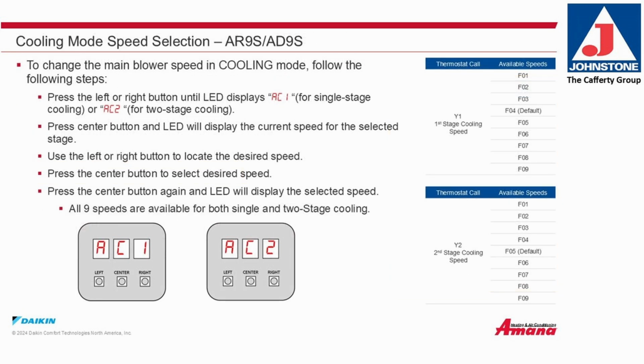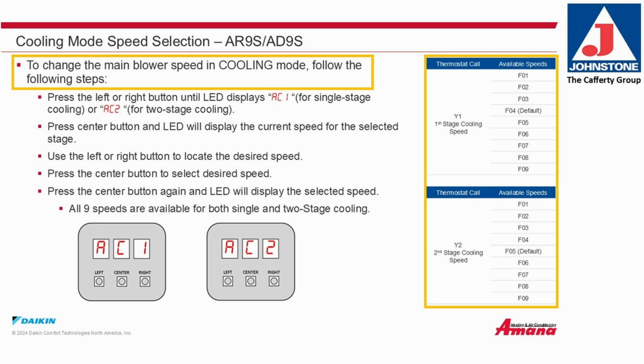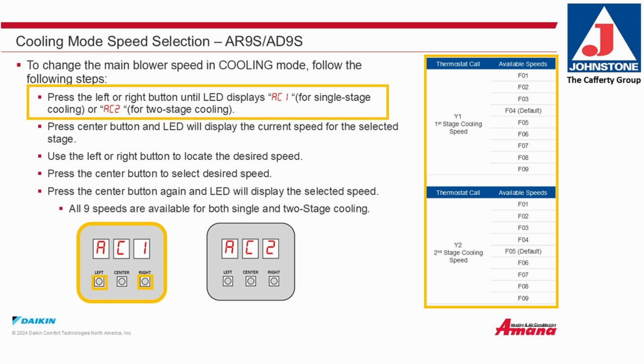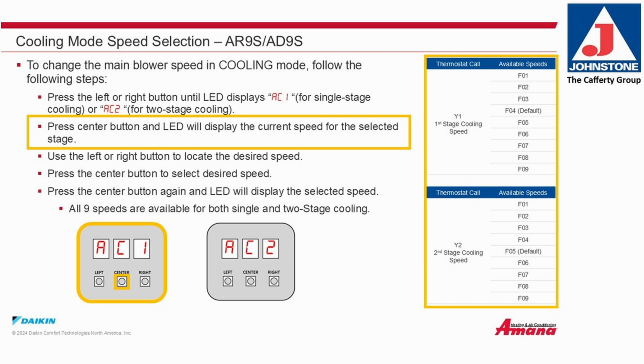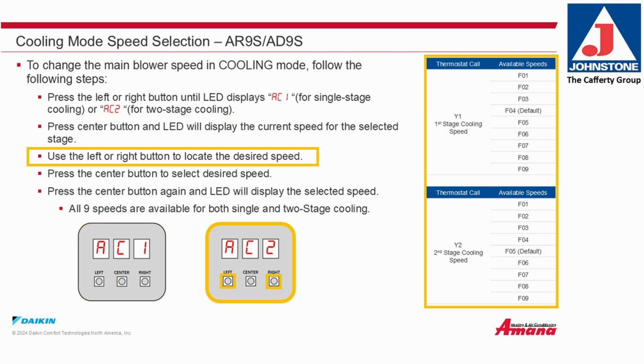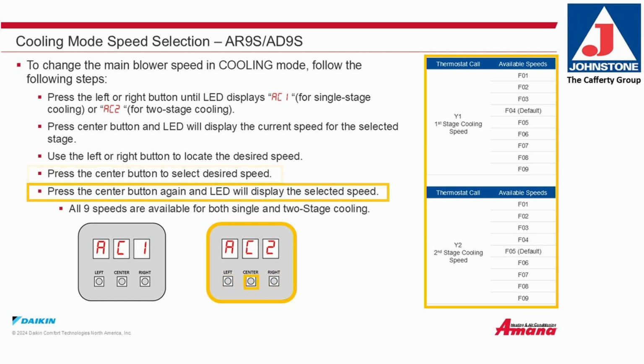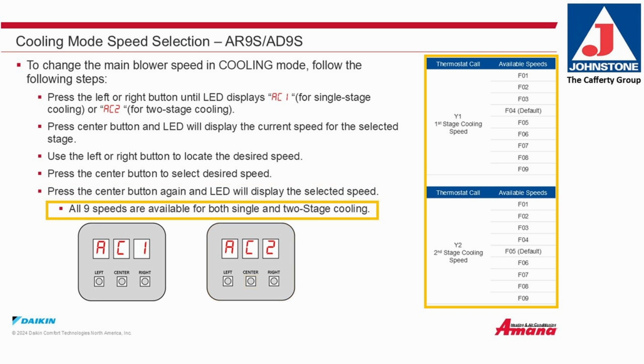Cooling mode speed selection. To change the main blower speed in cooling mode, follow these steps. Press the left or right button until the LED displays AC1 for single-stage cooling or AC2 for two-stage cooling. Press the center button and the LED will display the current speed for the selected stage. Use the left and right buttons to locate the desired speed. Press the center button to select the desired speed. Press the center button again and the LED will display the selected speed. All 9 speeds are available for both single and two-stage cooling.